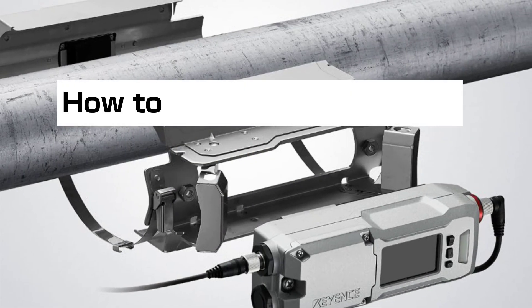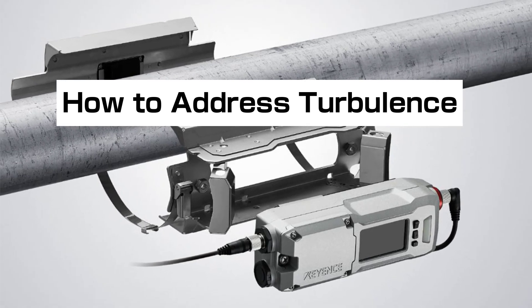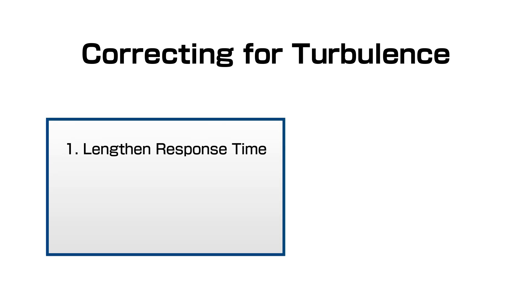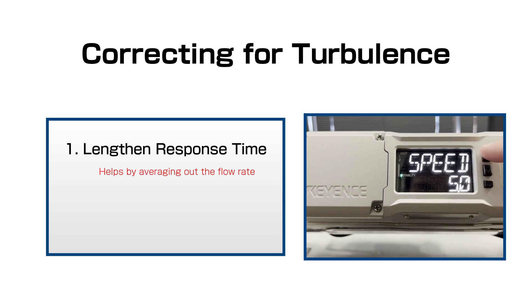Now that we know some typical reasons why an ultrasonic clamp-on flow meter might become inaccurate, let's see how the FDR series addresses these concerns. For issues with turbulence, there are two actions to take. The first is to increase the response time on the sensor, which will help it average out what it sees inside the pipe — perfect for making the flow rate reading steady when flow is turbulent. You can find the response time setting by pressing and holding the mode key, then briefly pressing mode until you see 'speed', which can be adjusted with the up or down arrows. A longer response time will average out the flow rate reading more than a shorter one, which is ideal for rapid turbulence.